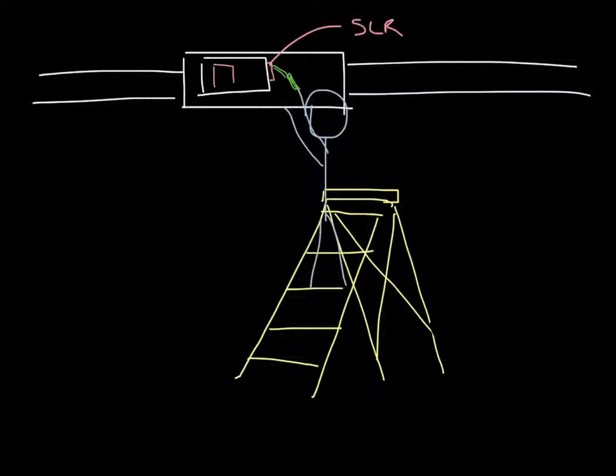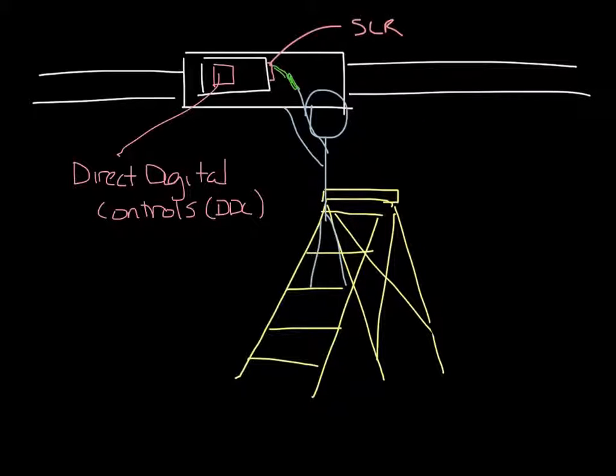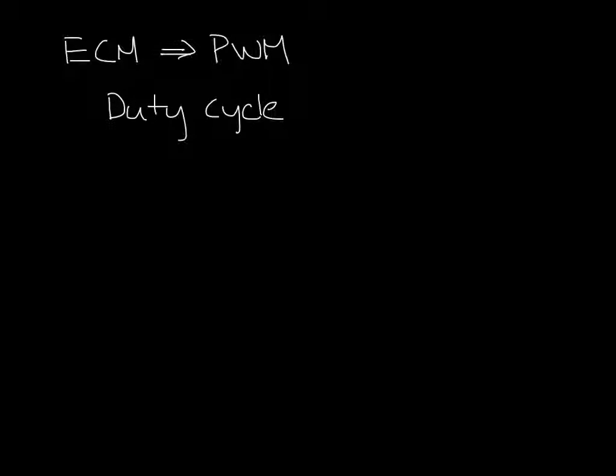But most fan boxes these days have a direct digital controller, or DDC controller, on them. So it'd be much easier if the controls of the fan box could talk to the motor and tell it to speed up or slow down. In a fan box with an ECM motor, they can. This happens through the PWM controller. Fan boxes with ECM motors have a PWM instead of an SCR. The PWM serves the same purpose, and in fact you can get a manual PWM that allows you to adjust it with a screwdriver on the side of the box. The PWM gives you more information than an SCR though. You can get RPM of the motor and the duty cycle. The duty cycle is the percentage of a period that the PWM signal to the motor is active.